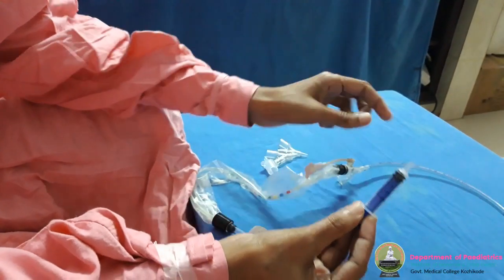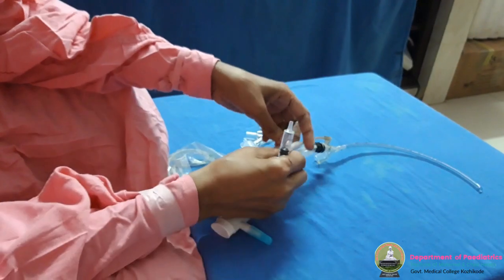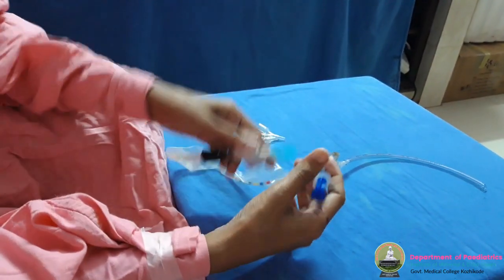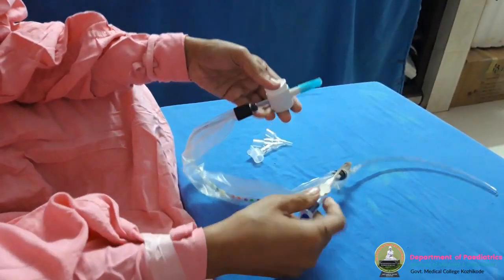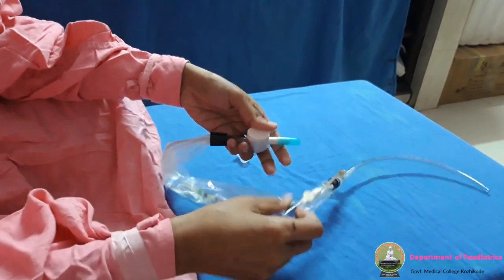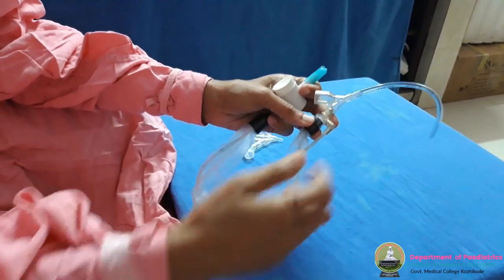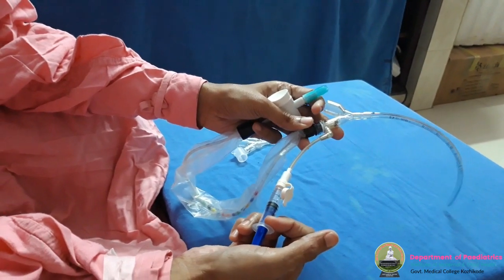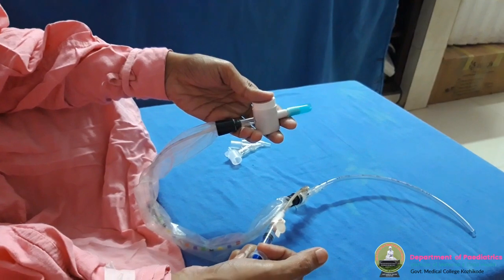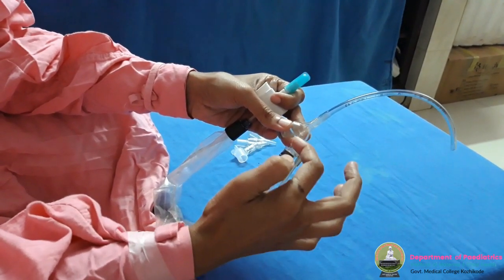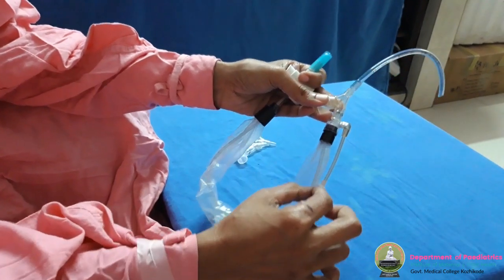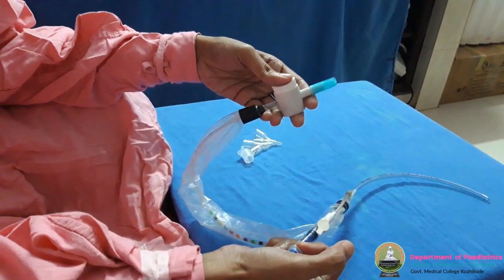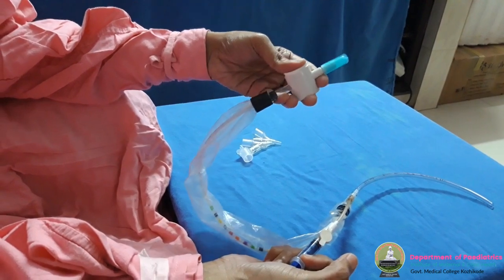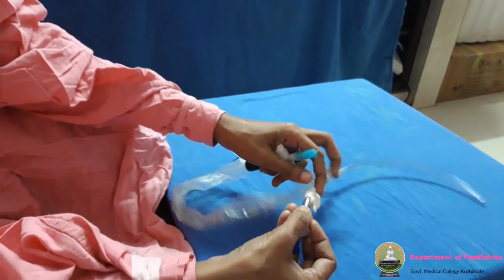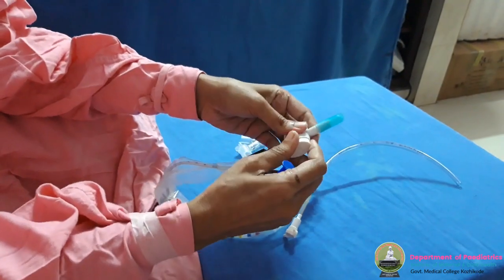A 2 cc syringe with 1 ml or 2 ml saline in it. Attach it to this port and keep on compressing this switch. The suction should be working, and with that you should instill a small amount of saline into this chamber, say 0.5 ml. It should be inserted, and at the same time it should be suctioned out. So in aliquots of 0.5, you instill saline into this chamber. It will get rotated in the chamber with all the secretions in the saline, and it will be drained through the catheter. So the catheter rinsing is also completed with this procedure. So insert 0.5 cc of saline and compress it so that the catheter is also cleaned well. After that, you can remove the syringe and close this port and close this area also.